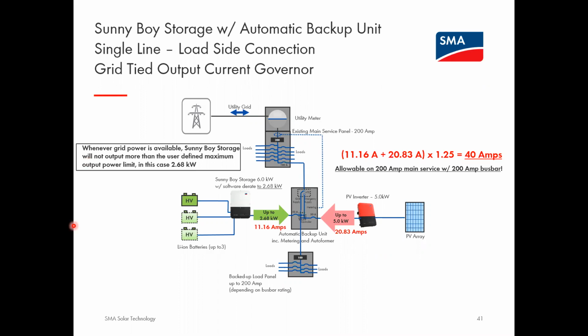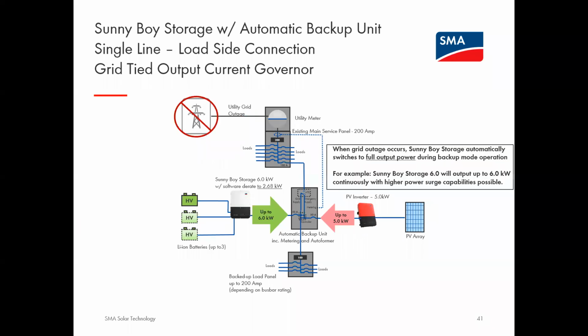But of course, what about the backup scenario? What this current governor allows you to do is, when you lose grid power, that restriction, that software derate, is automatically lifted. And now the SunnyBoy Storage is able to output its full nameplate power rating plus the surging capabilities, in addition to whatever the PV inverter is able to output, to supply a backed up load panel.